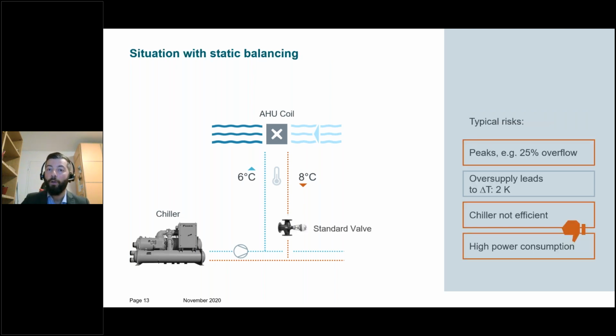So what happens when you control this loop with a static control valve? Well, obviously, you're not going to have just one coil in your hydronic distribution system. You are going to have many coils. The system will be more complicated, and there are many factors that influence the energy demand, and therefore the return temperature. For example, at the beginning of a meeting with a large audience in a conference room, you need extra capacity. Or at the beginning of the week, when you switch from reduced comfort to normal mode, you need extra capacity.